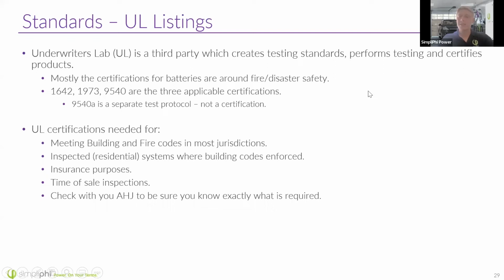So I'd say increasingly, inspectors are looking for UL listed products only. Your batteries needing to meet UL 1973 is almost a given across all jurisdictions, whereas UL 9540 certifies the system as a whole, so the batteries and inverter and any other components all together will be certified under 9540. This is not as commonly required, it's a little more rare, but it's growing in popularity.